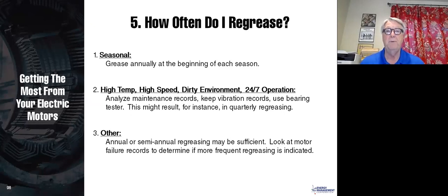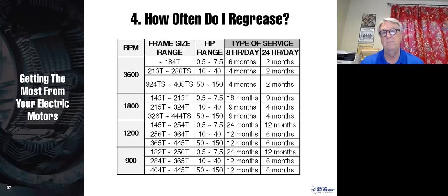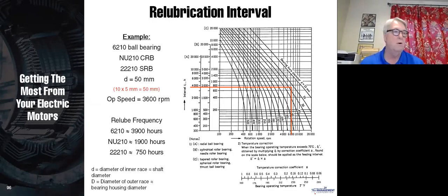If you have high temperature, high speed, dirty environment, or a 24/7 operation, then sometimes you can use maintenance records and actually determine how often they need to be testing on the basis of measuring the vibration or looking at the temperature of your bearings. Or you can use annual or simply semi-annual greasing. And a lot of people do this, but I would really recommend that you use number 4 or number 3 here where you have these curves.